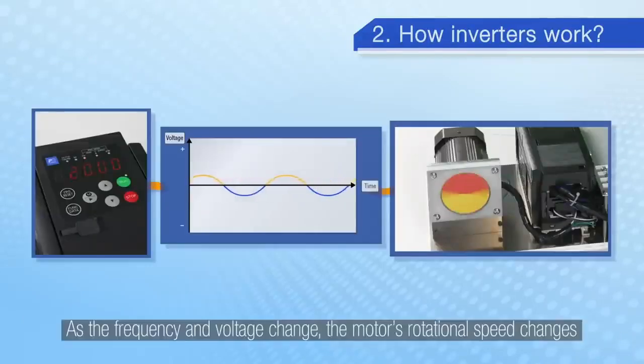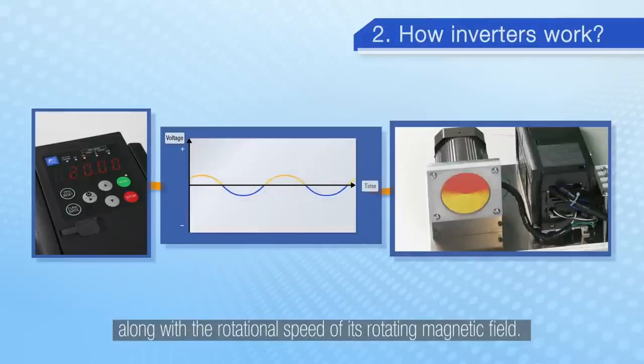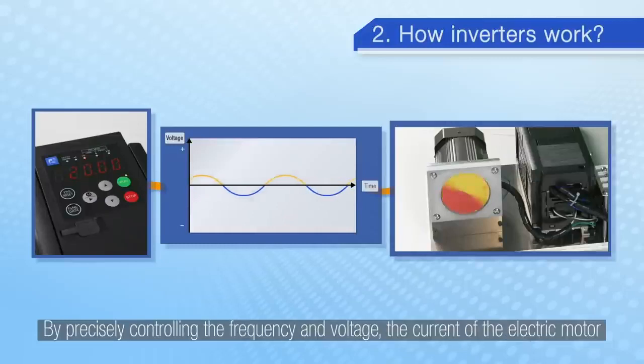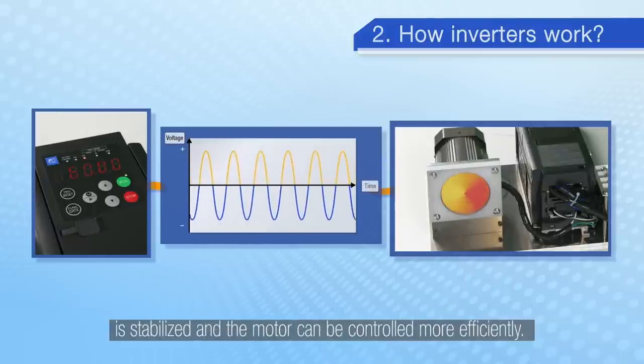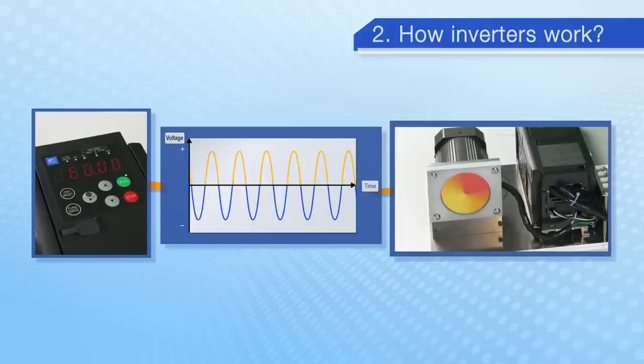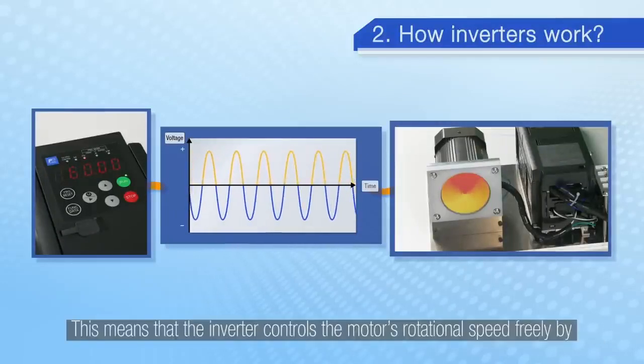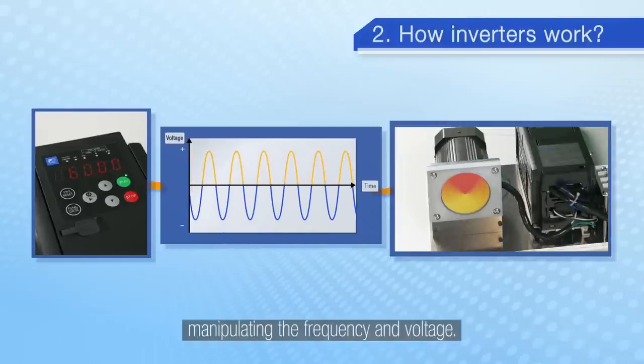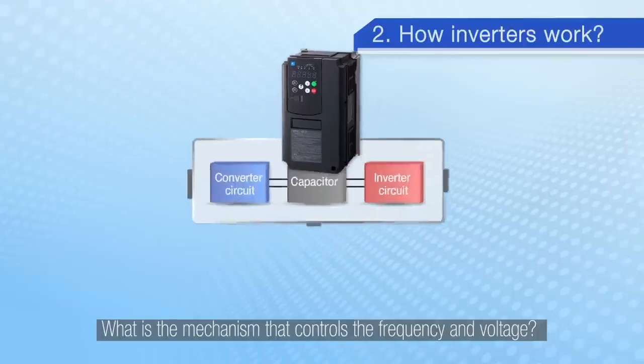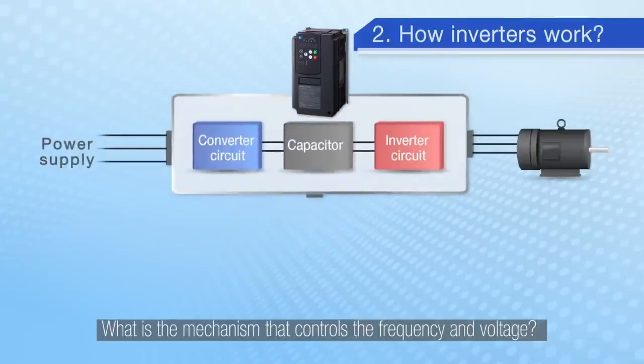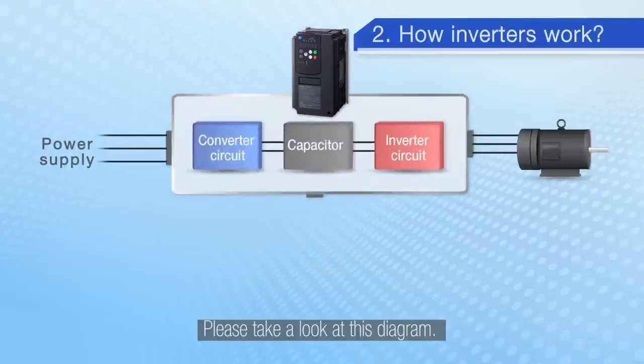As the frequency and voltage change, the motor's rotational speed changes along with the rotational speed of its rotating magnetic field. By precisely controlling the frequency and voltage, the current of the electric motor is stabilized and the motor can be controlled more efficiently. This means that the inverter controls the motor's rotational speed freely by manipulating the frequency and voltage. What is the mechanism that controls the frequency and voltage? Please take a look at this diagram.